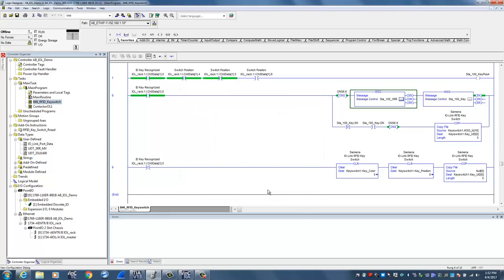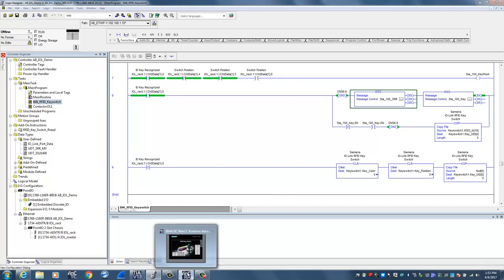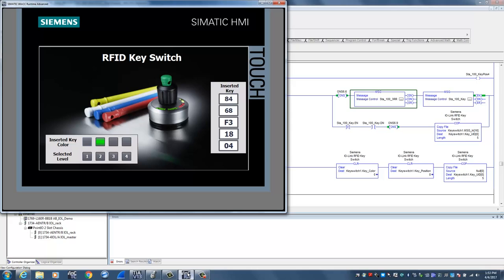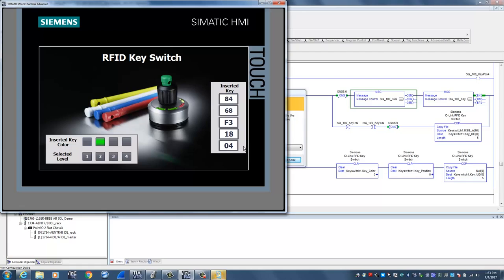Once I have that information—say, for the RFID key switch—we can now also create some HMI screens using a Siemens HMI, and that's what I've done here on our project. So here's our HMI running, and you'll see no key is currently inserted into the reader. As I insert a green key, you'll see a green key has now up to two levels of available access. And also when I inserted the key, you'll see on the right-hand side of the screen where it says 'inserted key,' here's the unique hex address that's associated with that green key. Even if you had multiple green keys, each one would have an individual hex code associated to it.